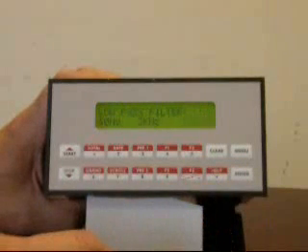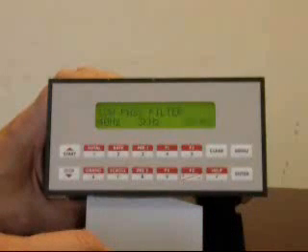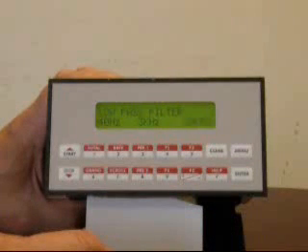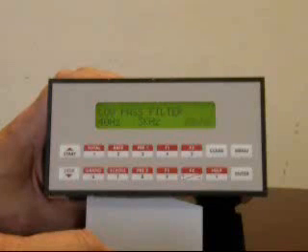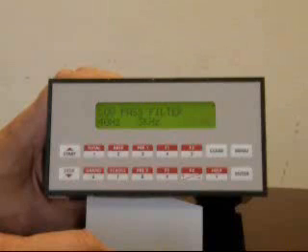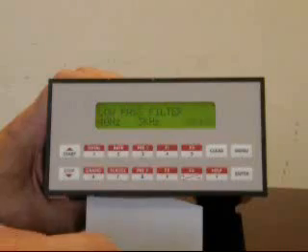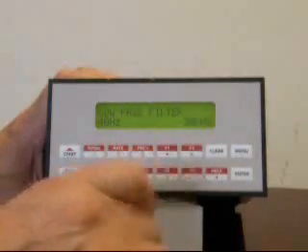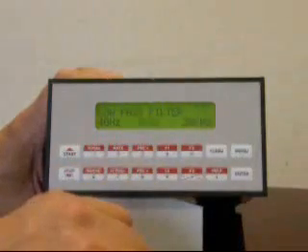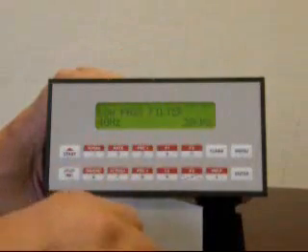Next, you'll notice there's a menu that offers you several different low pass filters. These are basically noise rejection settings to eliminate the possibility of picking up higher frequencies than what might be actually output by the flow meter. The 3 kilohertz setting is commonly used on turbine flow meters.